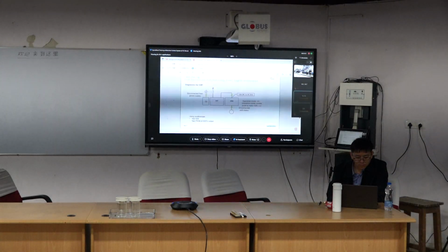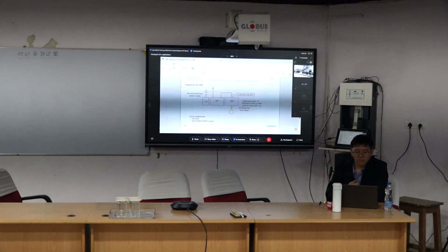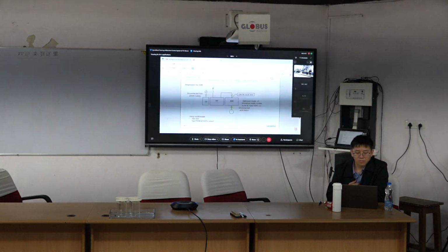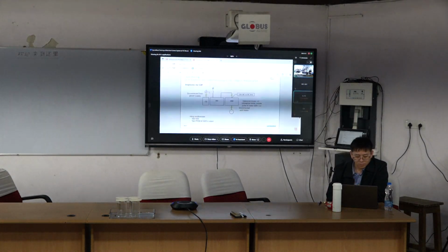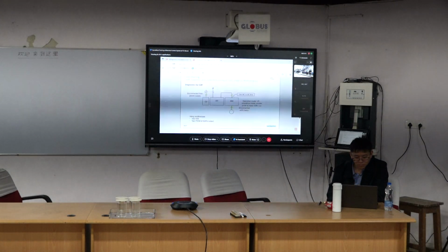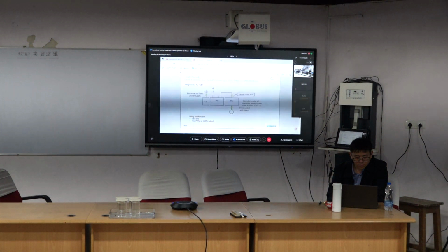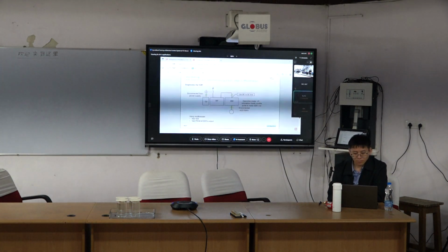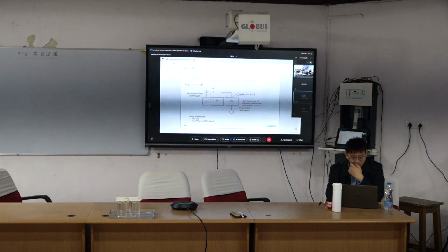Simulation mode of the drive converter is provided for the test. Yes, you must disconnect it from the power grid, and you must power on the control power 24 V to the DC link.